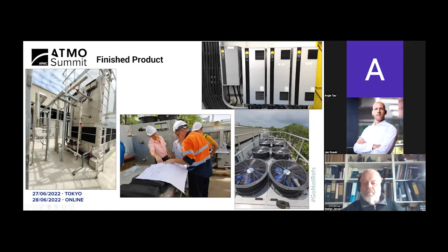These are the compressor VFDs. So these are the booster VFDs, and these are the 3 second stage machines. There's actually only 2 second stage machines, but one is fitted with a large motor, so it can run dual duty, low temperature or high temperature stage. You know, the detail here, these are the purge reservoirs. So this is where the air that gets into the plant is collected and taken to the purger.